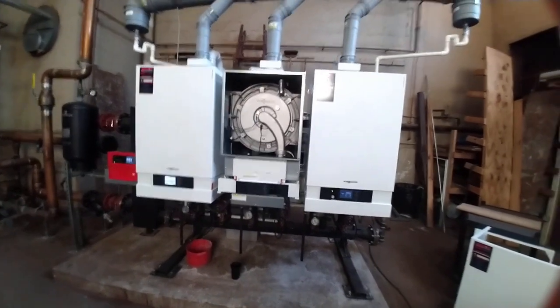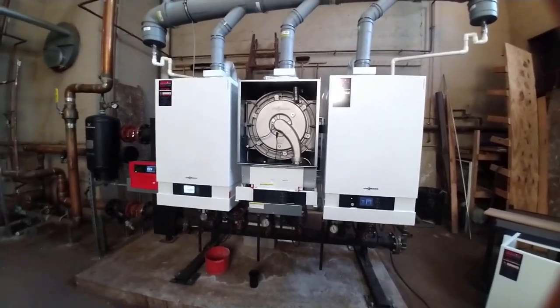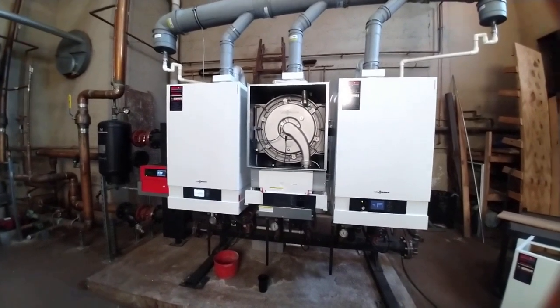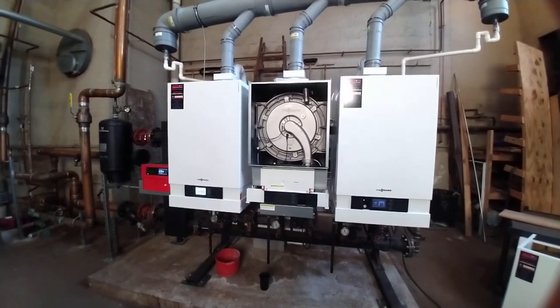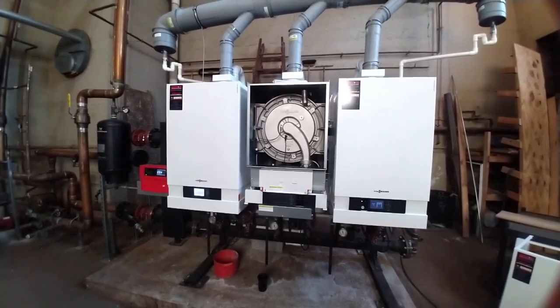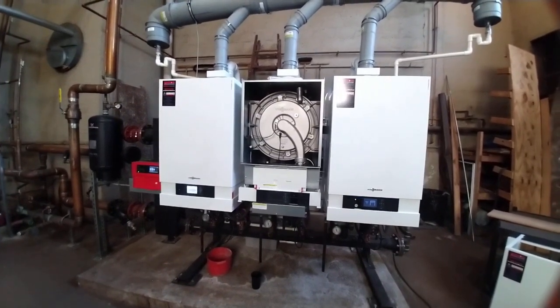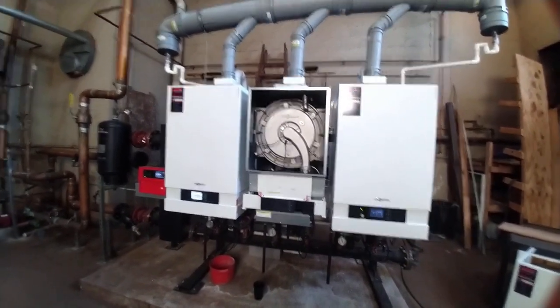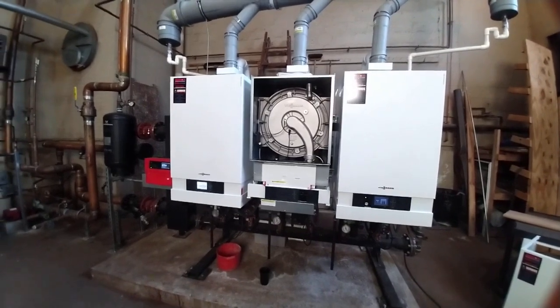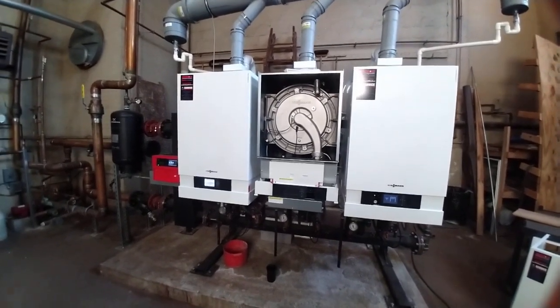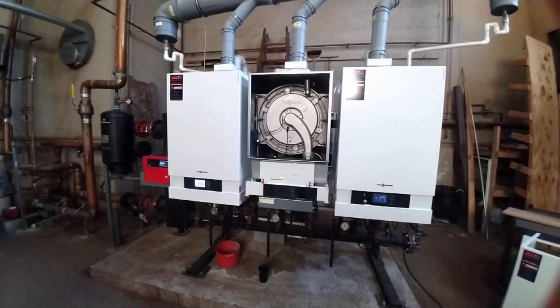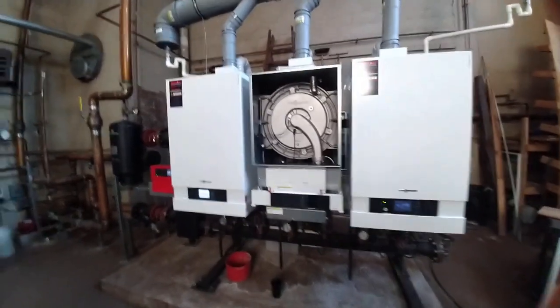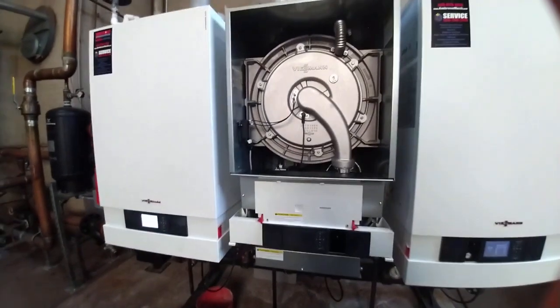Most common problem we have with these Viessmann boilers is that very few owners want to allow us the time to do the proper maintenance and service because they seem to just keep on running. So we have to do our due diligence and make sure that they understand that just because a system's running doesn't mean it doesn't need maintenance, doesn't mean it doesn't need to be checked on an annual basis.